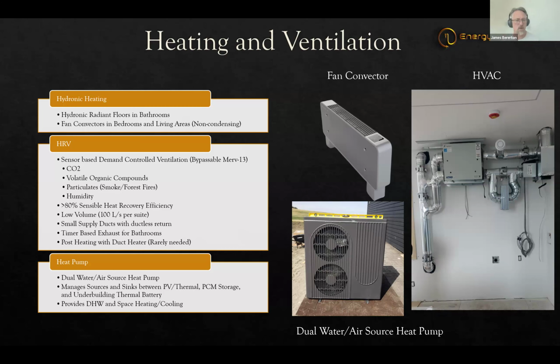It has 80% sensible recovery at its maximum efficiency. In the wintertime it'll do cycles and not be quite as good as that, but we have a really interesting control system on it. We even shut off the bathrooms when we're trying to purge the kitchen living area, then turn the bathrooms on full when a motion sensor detects someone in the bathroom. So it's very much demand controlled even in those other use cases.